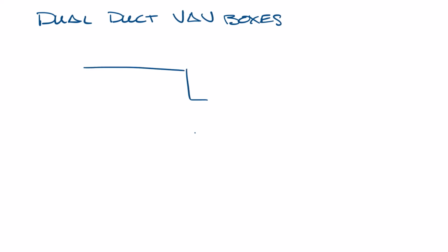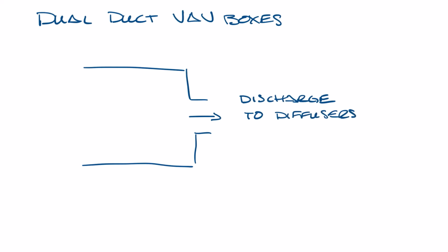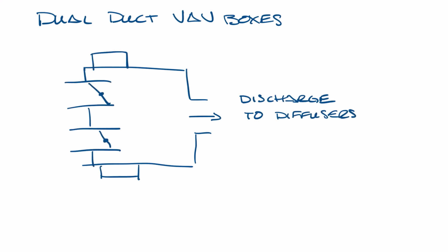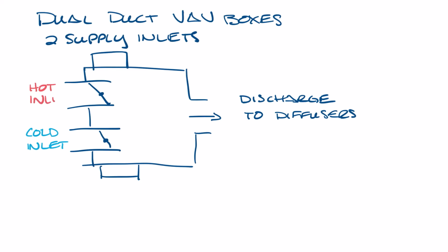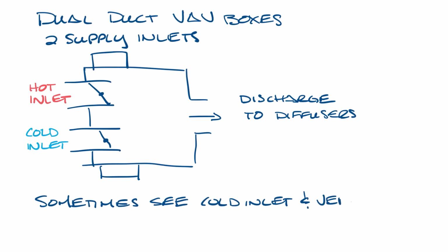Dual duct boxes aren't as popular as single duct and fan boxes, but you will run into them every now and then. Like all boxes, a dual duct box has a discharge that is ducted to the diffusers or grills in the space. The difference is that the dual duct box has two supply inlets, ducted to the supply air system. One inlet is ducted to cold air and the other is ducted to hot air. You might also see some dual duct boxes that have a cold air and an outside air inlet for ventilation.